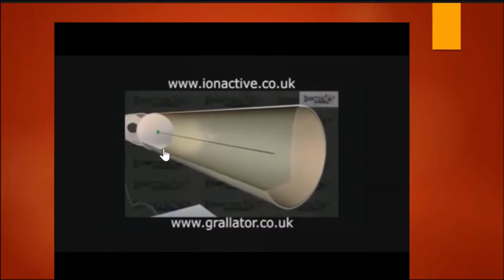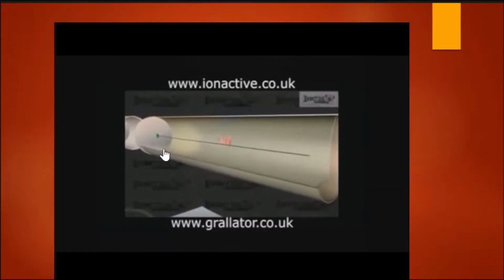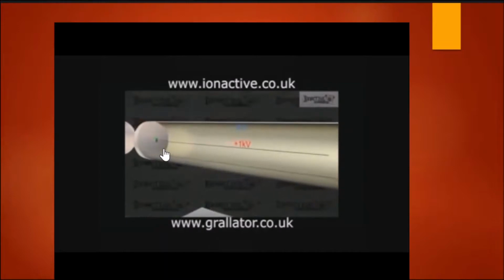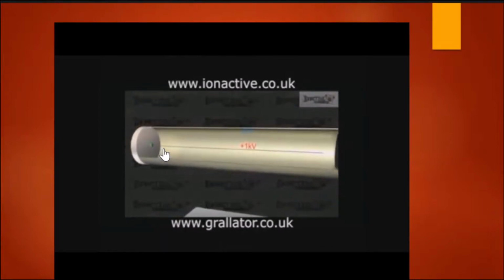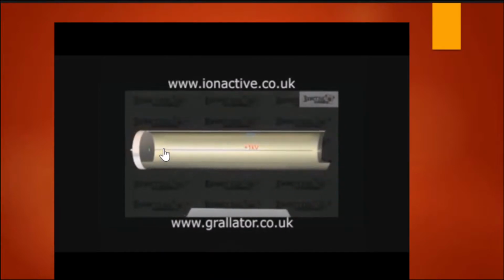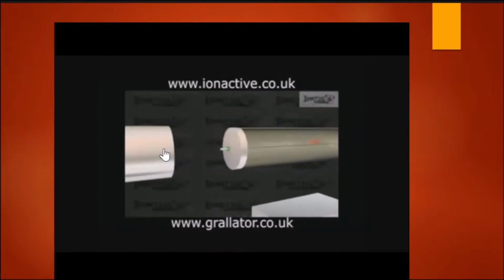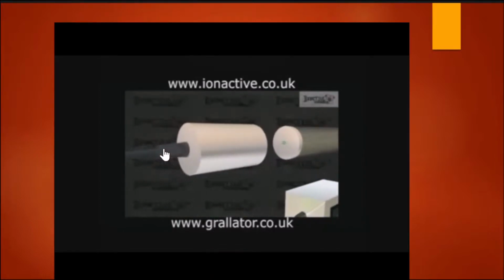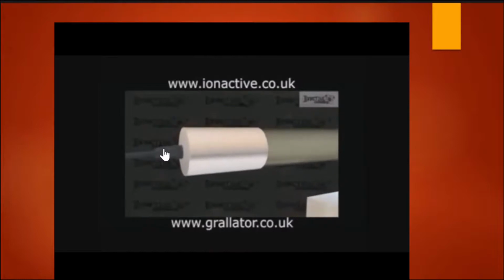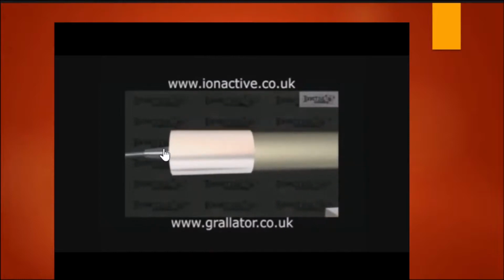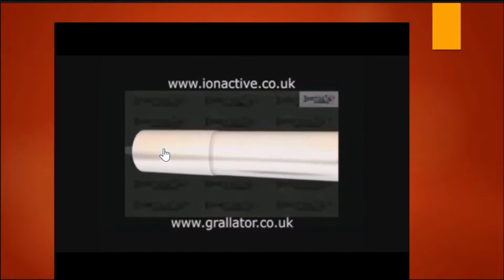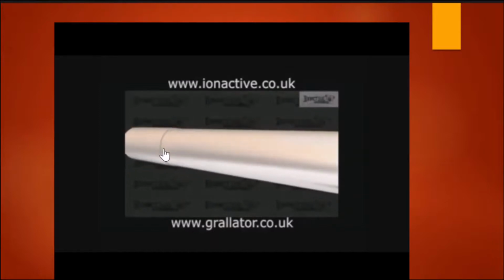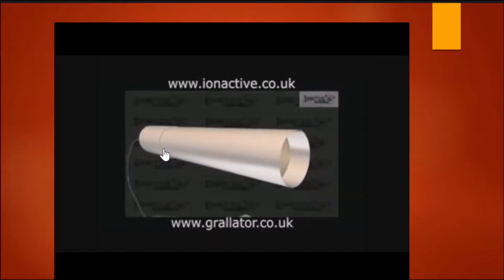The inner wire and the outer cylinder are maintained at a potential difference of about 1 kilovolt, and in the absence of radiation, no current can flow through the inert gas between the central anode and the outer cathode. The connections are made via wires into a connecting housing that fits over the rear of the tube. An outer tube guard will typically screw onto this to protect the actual GM tube.